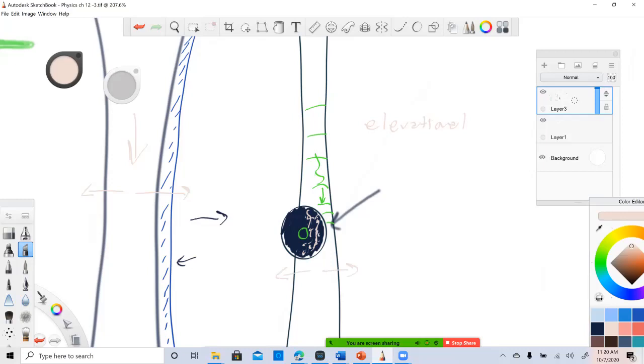We assume that the plane of our ultrasound image is razor thin, however, that is not always correct. The beam has a measurable thickness that can vary with depth. When the slice is thick, structures above and beneath the assumed razor thin plane create reflections that appear in the image. So we expect that cyst to be black, and it's not black. Why? This is one of the reasons. Slice thickness.